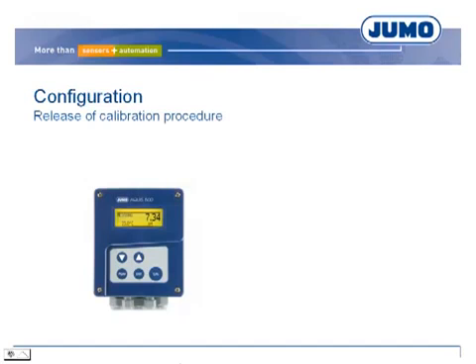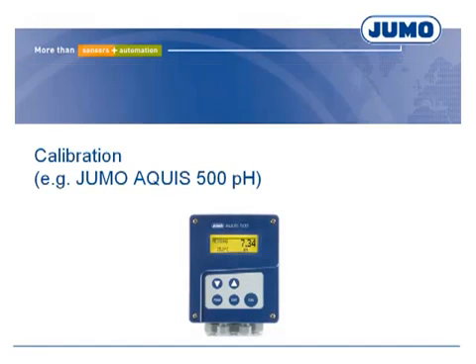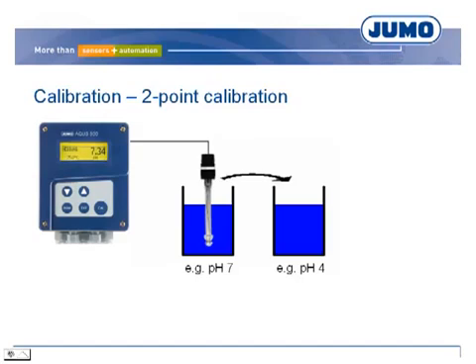pH measuring circuits are calibrated with three different methods. The most often used procedure is the two-point calibration, which is possible on the transmitter. In a pH measuring circuit an offset is possible, usually resulting from the reference electrode. Furthermore, the sensitivity gradually changes due to the pH electrode. Calibration compensates both offset and change of sensitivity. Buffer solutions — solutions with defined pH values — are normally used. The two-point calibration is a standard method that compensates offset and slope, requiring two buffer solutions.